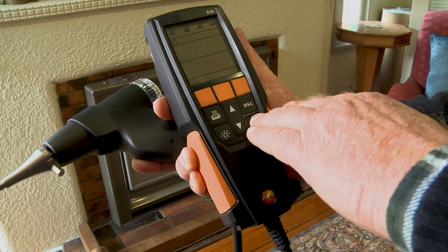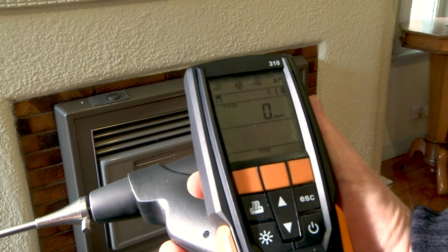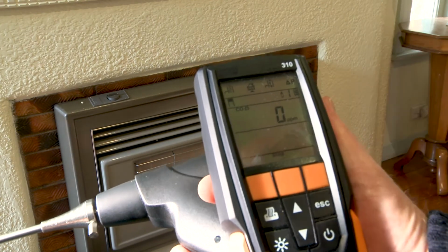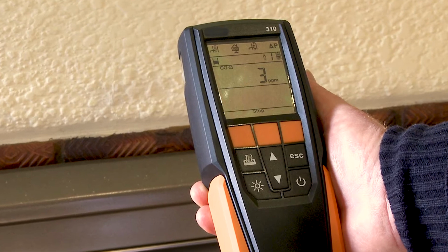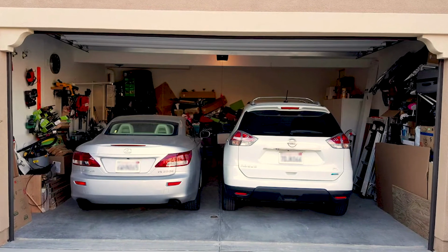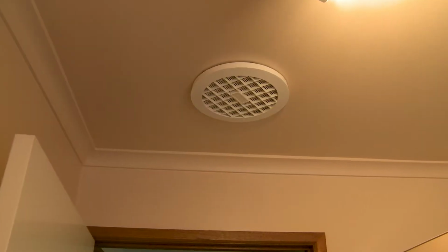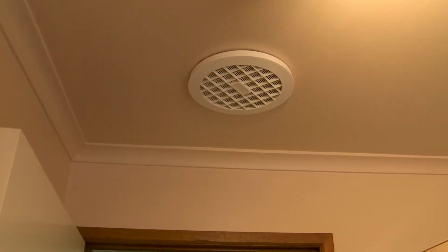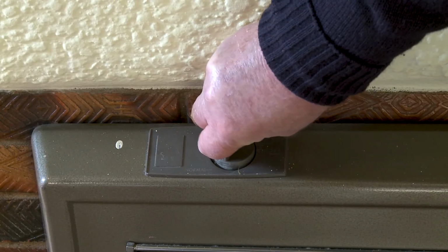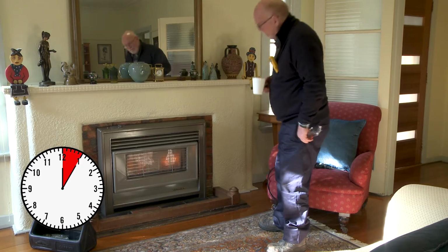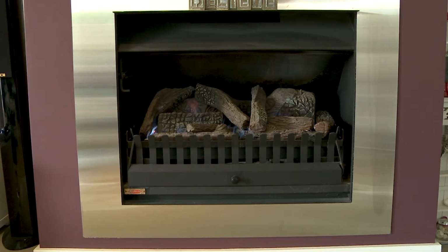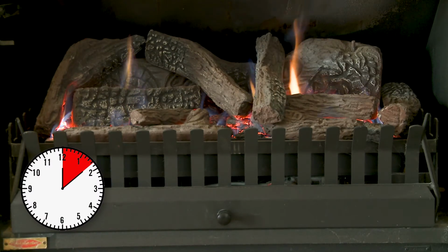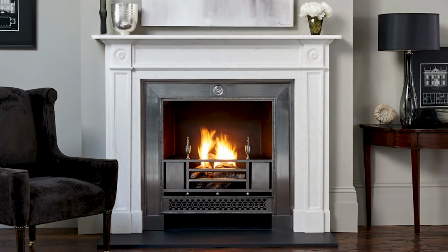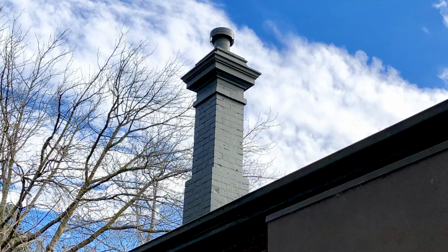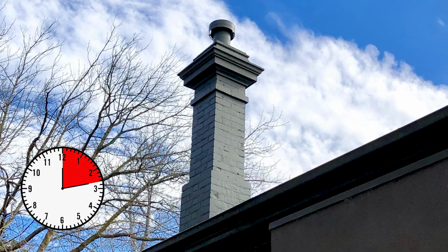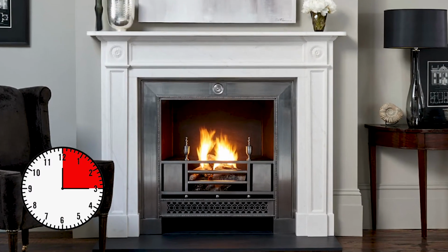Turn on your testing equipment in the room where the appliance is installed and record the background reading. Remember, background readings can be higher than 0 due to nearby car emissions or if someone has been cooking. With all extraction fans still running from your negative pressure test, turn on the gas appliance and set it to its highest setting. Leave it for 5 minutes before testing. Remember that Type 1 decorative effect appliances must be left on for at least 10 minutes before testing. If the appliance is installed in a fireplace using a masonry chimney as a flue, allow an extra 5 minutes before testing for spillage to allow the chimney to heat up and draw.